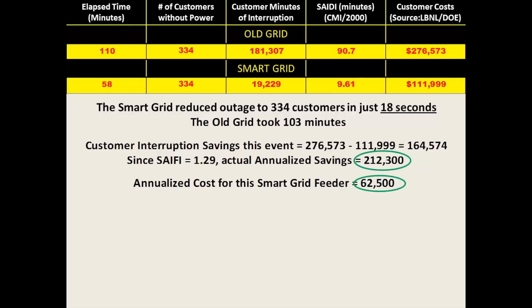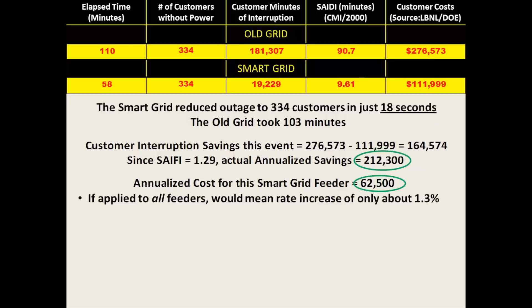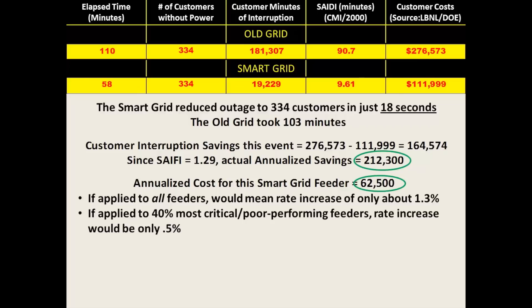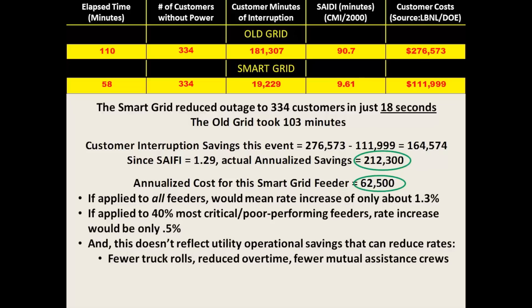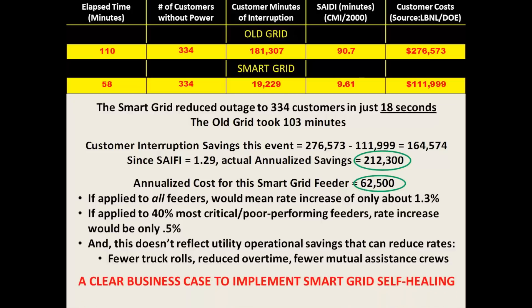Some might wonder: if we had to raise rates to provide this automation, how large would the increase be? Using average rates that industrial, commercial, and residential customers pay, if this technique were applied to all feeders, the rate increase would be about 1.3%. But this distributed intelligence can be applied incrementally — if used only on the worst-performing 40% of feeders, the rate increase would be just about one-half of 1%. This does not account for the utility's operational savings such as fewer truck rolls, reduced overtime, and reduced need for mutual assistance crews — all of which can be used to reduce consumer rates. There is clearly a very solid business case for implementing smart grid self-healing.